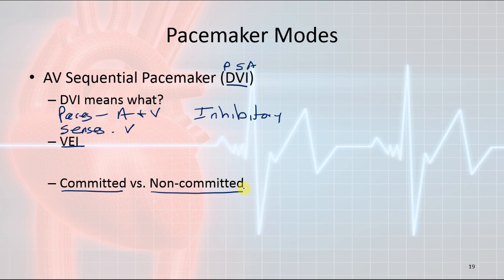In this case, the DVI pacemaker senses the ventricles, so it is using the ventricular escape interval. It is measuring the R to R interval in milliseconds. What happens if this ventricular escape interval expires? What does it pace? Well, it will pace the atrium and then it will pace the ventricle.